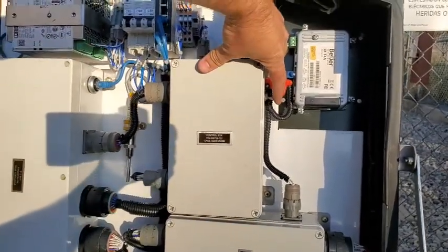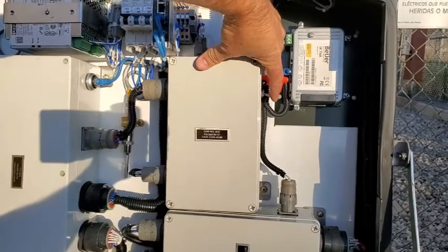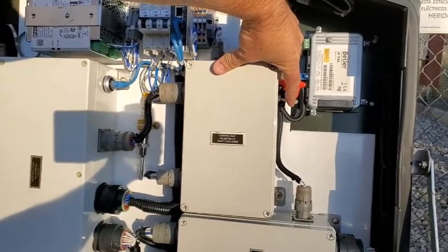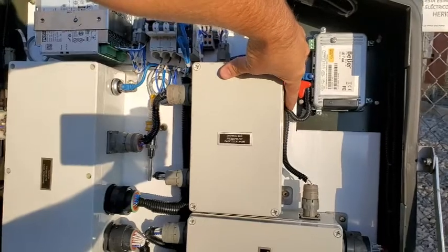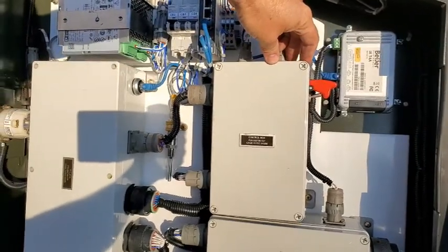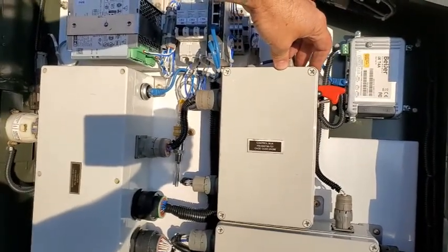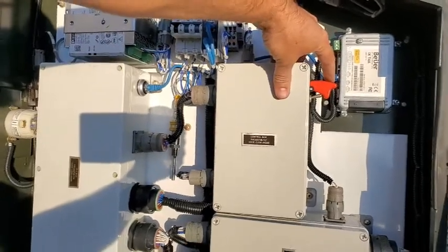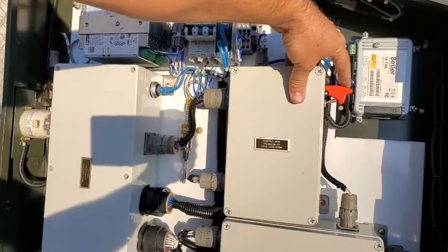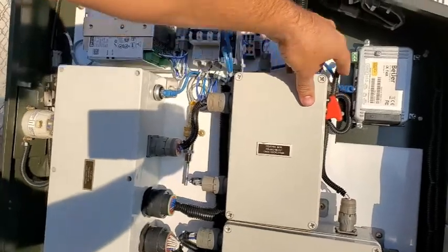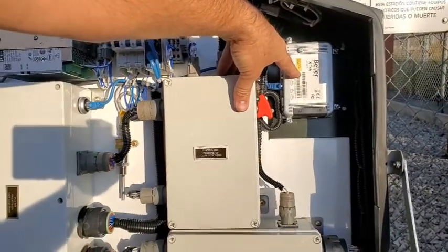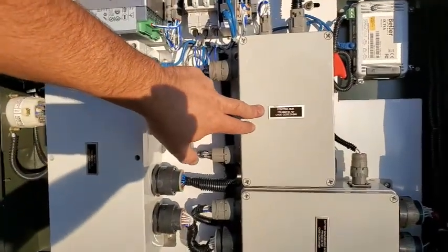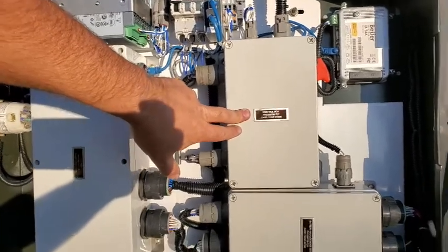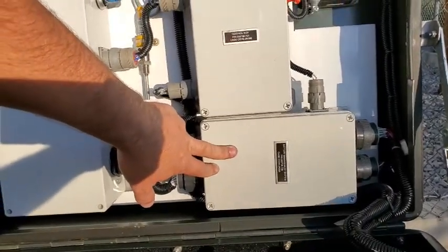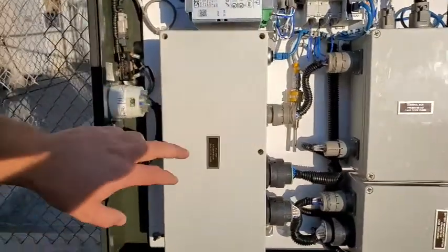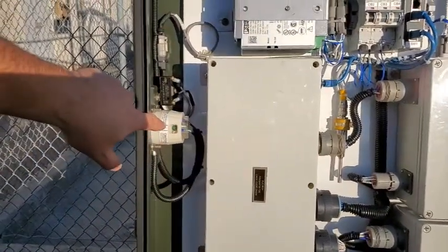In the event you cannot normally charge the battery pack with the charge switch due to low battery voltage, you need to turn this on, plug in your charging cable, and start charging the unit. Once you've charged it for an hour, you can go ahead and turn it off and close that. This is your HMI. Inside the control box, you've got relays. Down here is your battery management system, and over here is your PLC and your charging adapter.